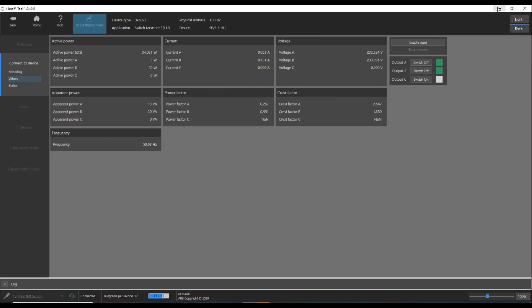Then we can see voltages, crest factors - everything's available there. If I go back to here now, you can see my power factor has corrected itself, and I've set up some alarms so it tells me when everything happens. My power factor now has gone from 0.4 up to 0.823 altogether. And again, you can see the energy coming through.